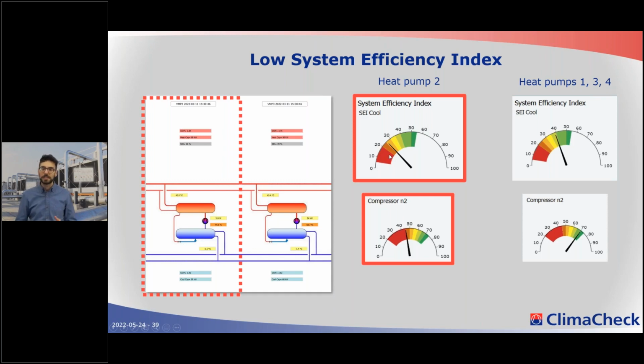In this case it's a big issue because we're talking about the compressor. The compressor is working terribly and is about to break down—it could happen any time. This is the result we got as soon as we started measuring. We could see directly that the compressor wasn't performing well, and because it was an extreme case, we had to stop the compressor.